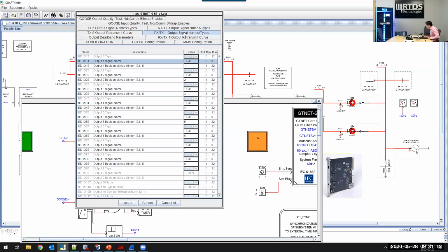Now let's see how the output variable TX2B is associated with the output data set that was created. So here we're in the output signal name types menu tab. After the data set is created in the SCD editor, the type of each enabled data attribute is automatically detected as here. So they are all Booleans. As you can see here, bit 1 to 4 of output variable TX2B are mapped to the Boolean data attribute 1 to 4. Which is expected. Again, ignore the other 4 outputs for this demo.